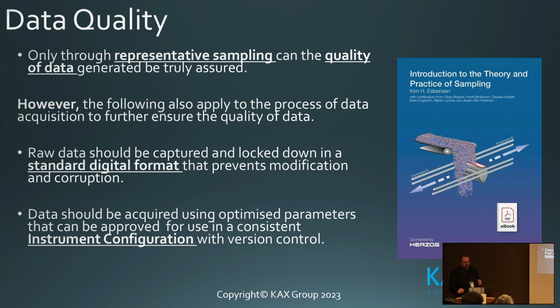Data should be acquired using optimized parameters that can be approved for use with consistent instrument configurations so that when the process operator pushes start on the process, it runs in a validated environment. And again, Steve and Phil have spoken at great length on how to optimize the systems to collect representative data and set outlier rejections so that only good data gets through to the model.